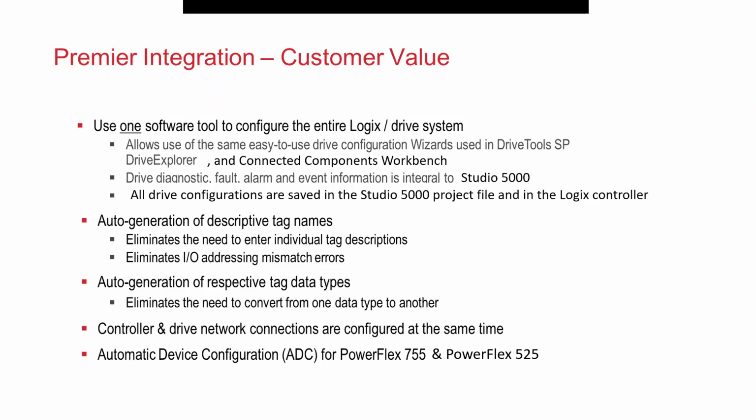Also, very important is when I configure, that's important, I'm not programming, I'm actually configuring. When I configure the add-on profile, I'm configuring the controller and the drive network connections, and they are configured at the same time. And ADC, automatic device configuration, is a subset feature for our PowerFlex 750 family and the 520 family as well.